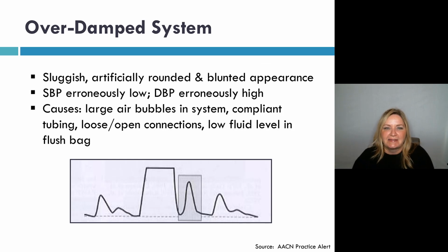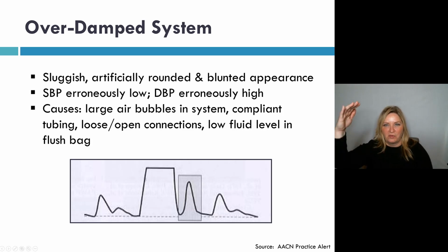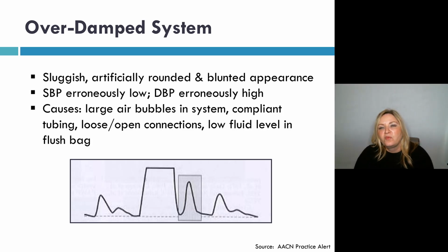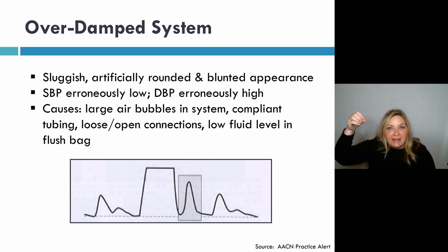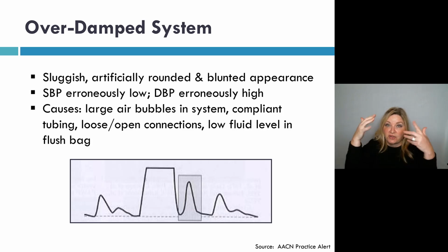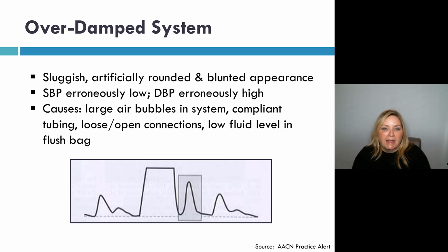Now an overdamped line: when you do your fast flush, you don't get those oscillatory waves. Your systolic will be erroneously low and the diastolic will be erroneously high. When you get this, look for air bubbles in your system. Do you have the right tubing? Do you have any loose connections? Maybe your fluid level is low in your pressure bag, so make sure your pressure is at 300 and that there's enough fluid in the bag. Or maybe the line has just been in for a long time.